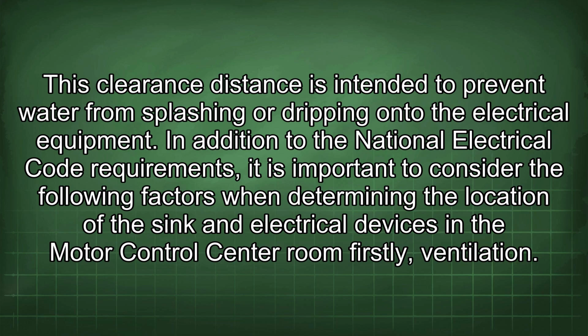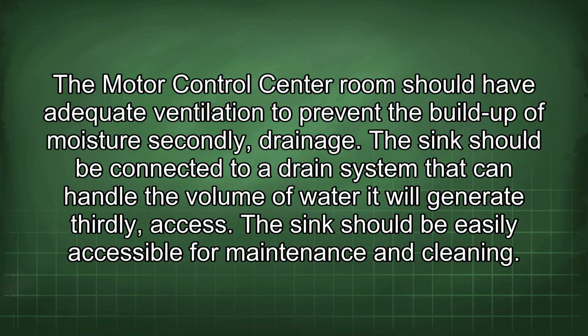In addition to the National Electrical Code requirements, it is important to consider the following factors when determining the location of the sink and electrical devices in the motor control center room. Firstly, ventilation. The motor control center room should have adequate ventilation to prevent the buildup of moisture. Secondly, drainage. The sink should be connected to a drain system that can handle the volume of water it will generate. Thirdly, access. The sink should be easily accessible for maintenance and cleaning.